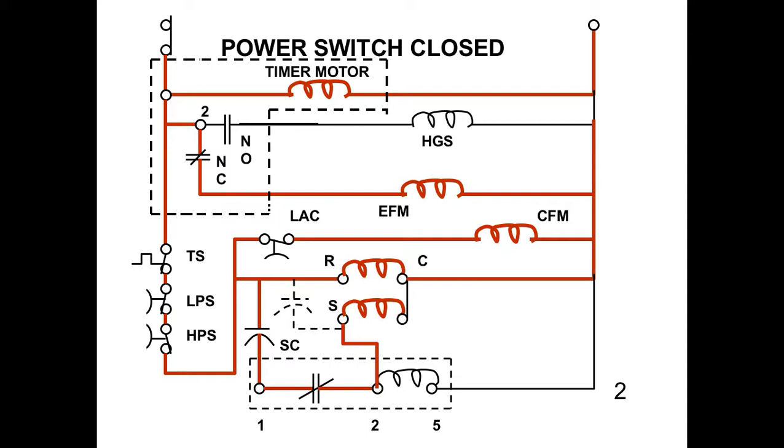So we close the power switch. Now notice the red on the diagram. The timer motor is energized because that's line-to-line. Our normally closed from pin 2 of the defrost clock allows our evaporator fan to energize. Our thermostat is calling for cooling, our pressure switches are closed. So our condenser fan motor, our compressor, run and start winding, because it's just starting up, is energized. The potential relay, which is down here at the bottom in the dotted lines, with the start cap in series with pin 1, 2, and the start winding, that is a brief moment in time. That is only energized as the compressor starts.